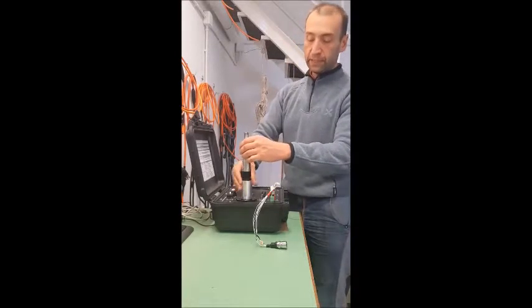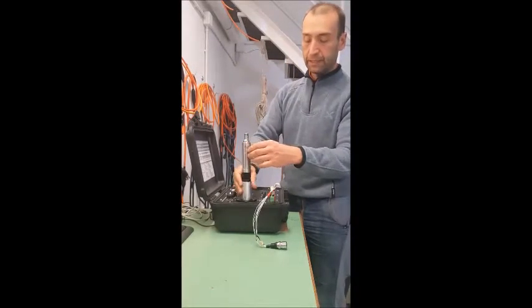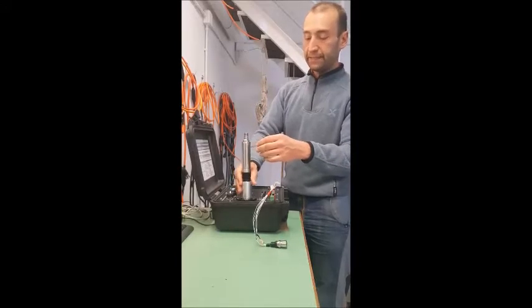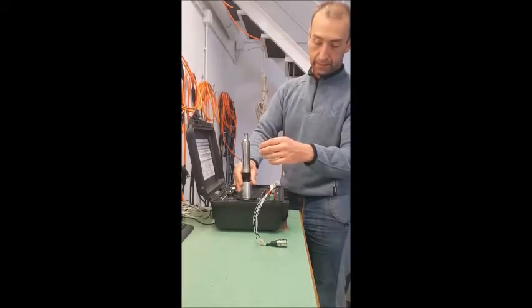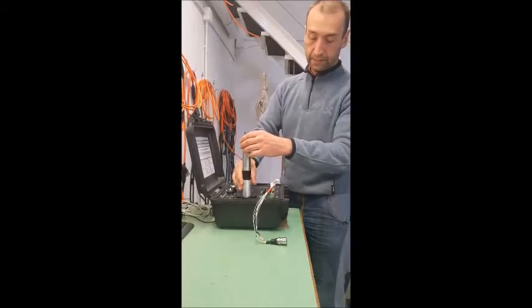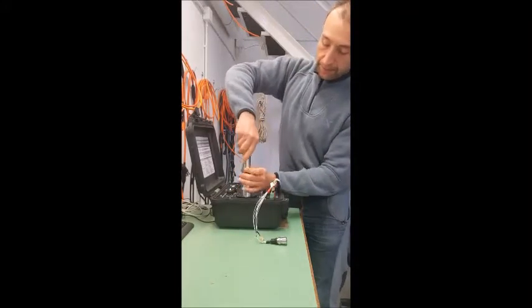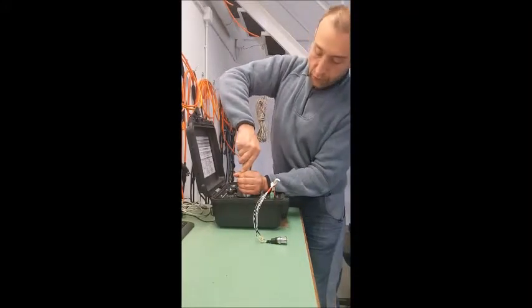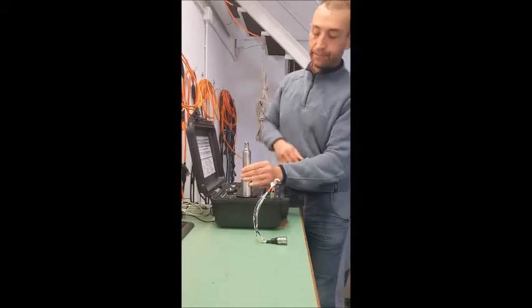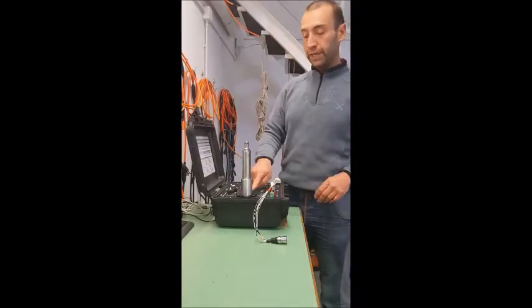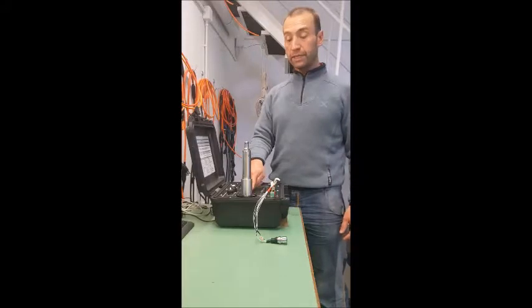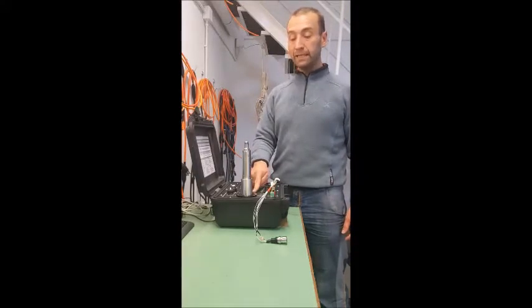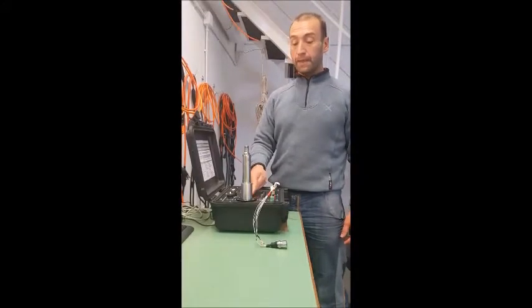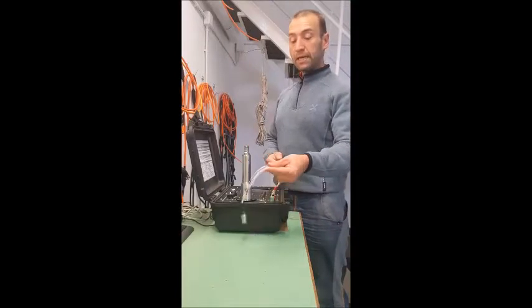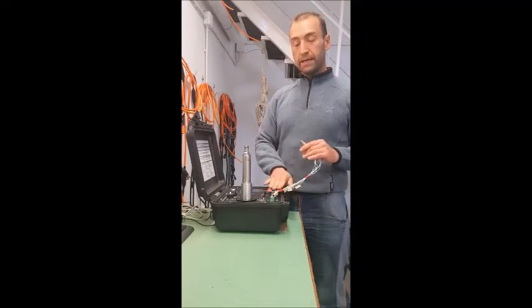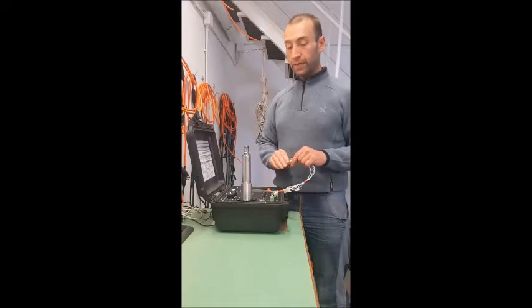Once the hydrophone is mounted inside the interface, it needs to go to the deep end of the chamber. Inside the chamber there is a speaker that creates an acoustic stimulus, and this stimulus is then read by the electronics inside the calibrator.